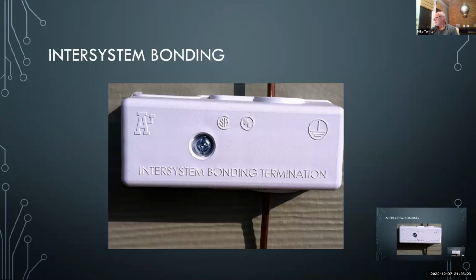Intersystem bonding. This is a requirement that came about, I'm not sure, a few years back, 2002 maybe. This is for the cable guy, the phone guy, where they used to put the little clamps on the cabinet. The worst thing they would do, I had a phone guy who would drive a ground rod on the other side of the house and tie his phone to it. That's terrible. That gives a voltage difference in grounding systems in the same house.